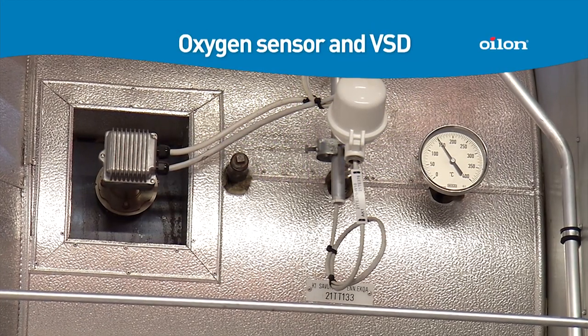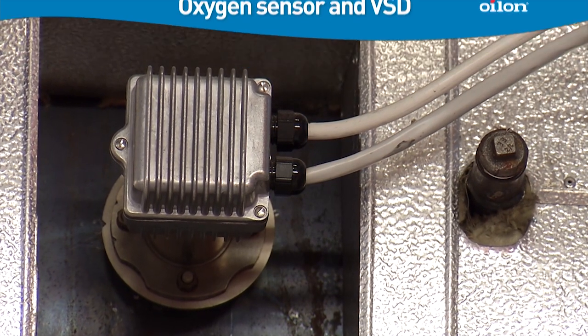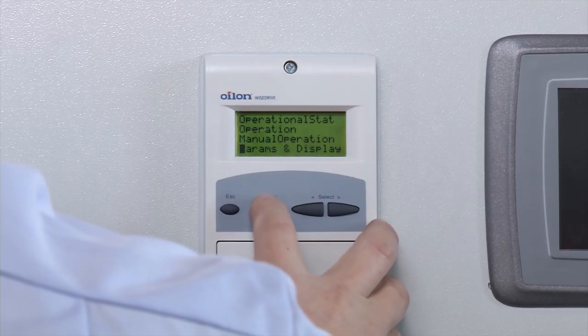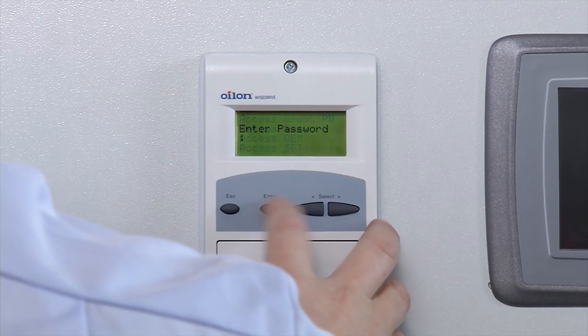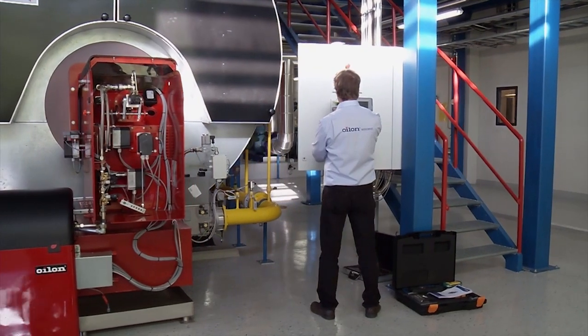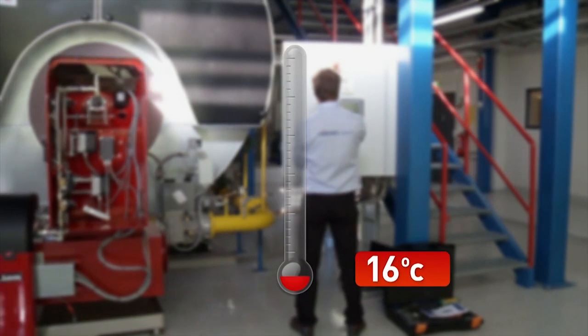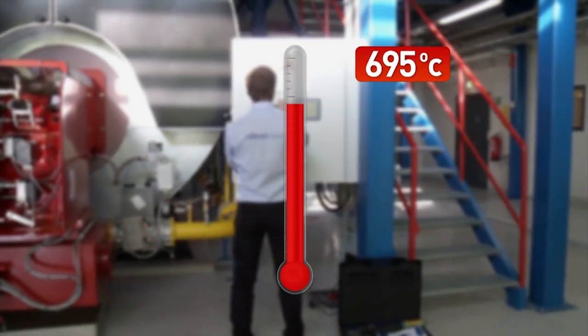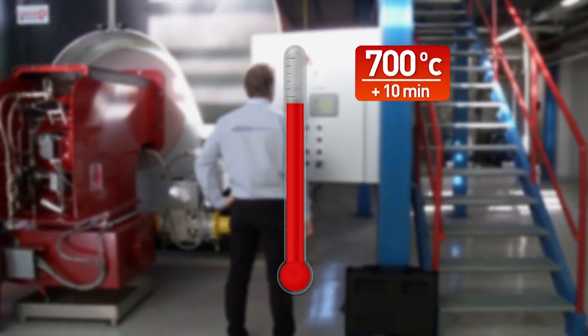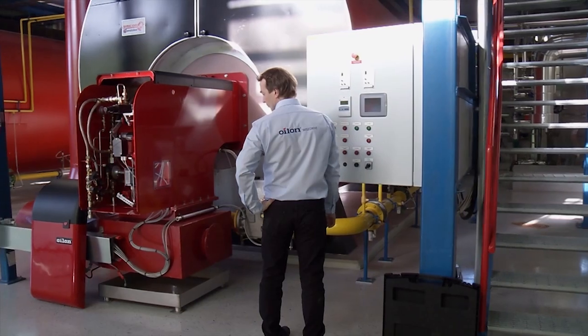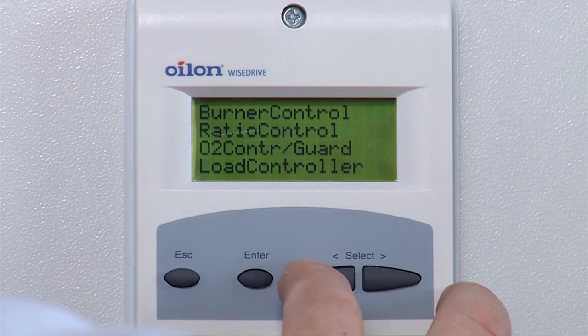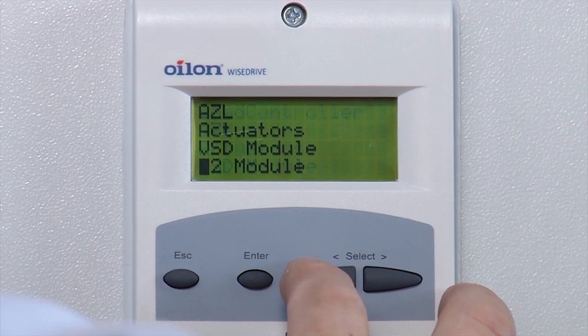The oxygen module and oxygen sensor increase combustion efficiency. They measure the residual oxygen content of flue gases. Activate the oxygen sensor during the first start-up to start heating. After the activation process, the oxygen sensor requires the temperature to reach 700 degrees Celsius. The oxygen module creates the required temperature itself — note that this can take a while. Oxygen module settings are in the menu under parameters and display. Select O2 module.